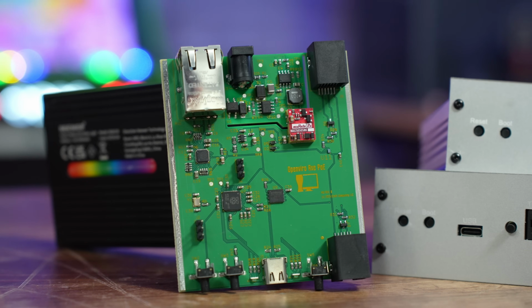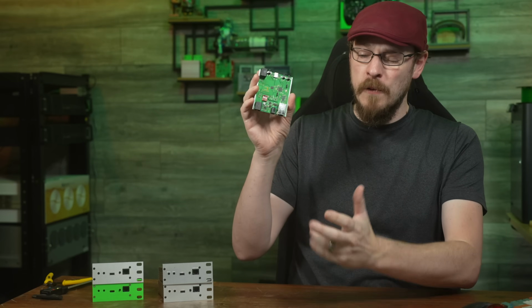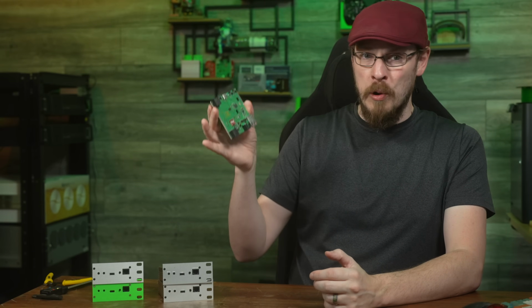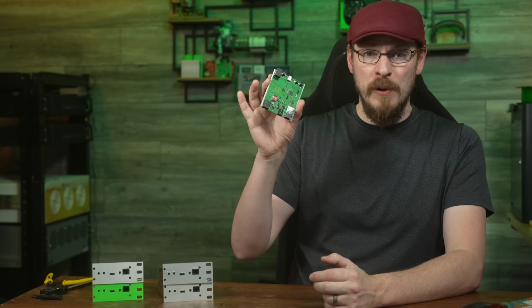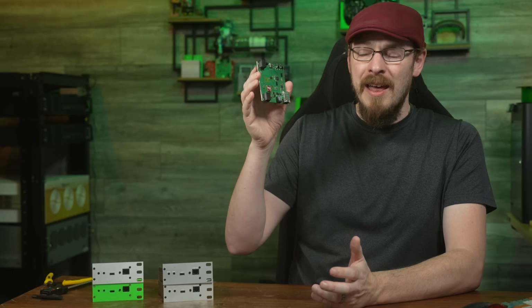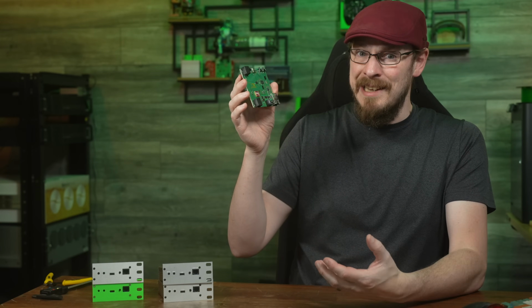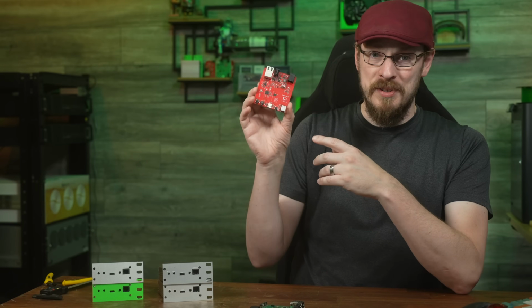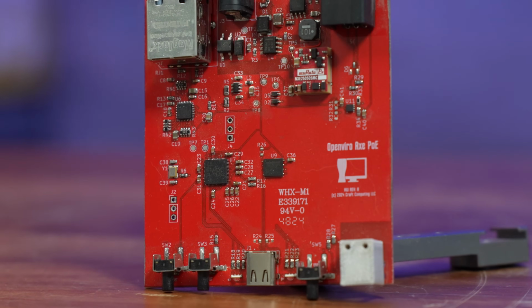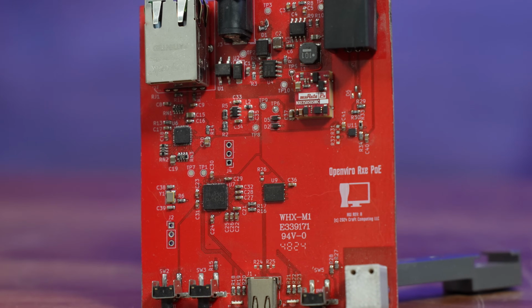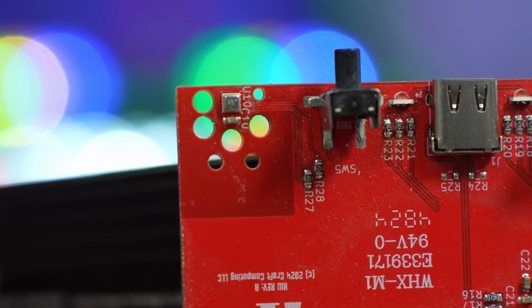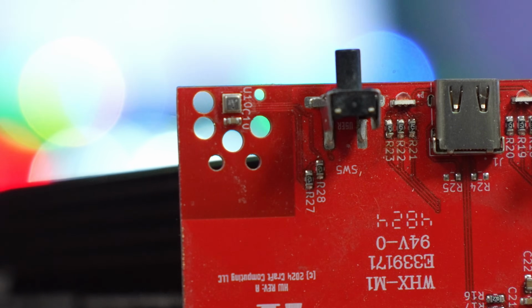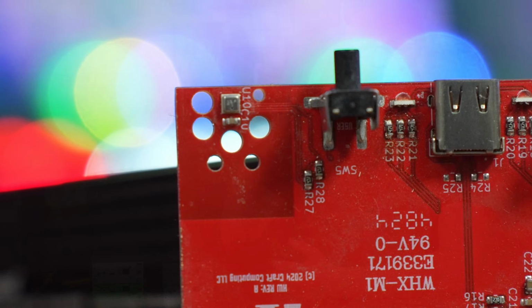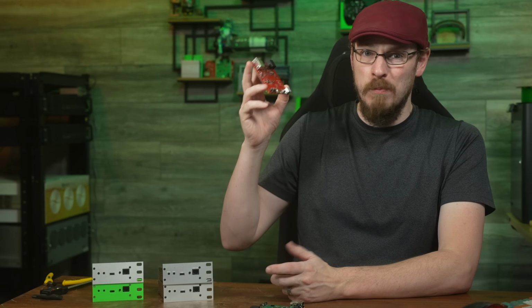That was actually a leftover design feature when we were working on integrating a temperature sensor directly onto the brain PCB. Unfortunately, when stepping down 54 volt power over Ethernet to either 5 or 3.3 volt, which is what the Rxe PoE runs off of, the unwanted byproduct of that conversion is heat. In fact, here is our very early prototype. You can tell because it's red. We mounted a temperature sensor right here on the front of the unit, but we wound up needing to remove the temperature sensor entirely as we were seeing nearly 6-degree deltas between the internal and external temperature probes. And on a product that's designed to be an accurate temperature sensor first and foremost, that just wasn't acceptable.